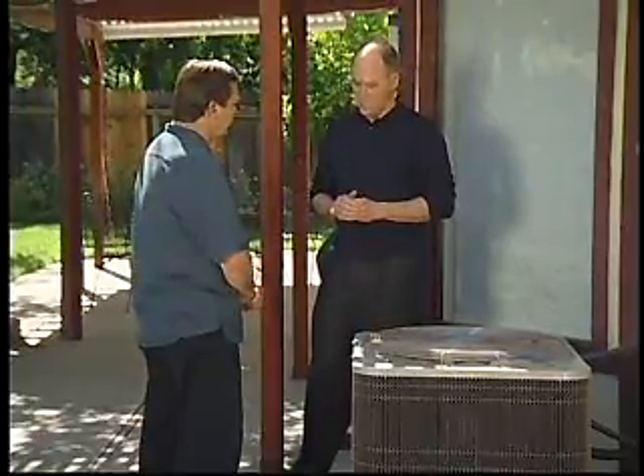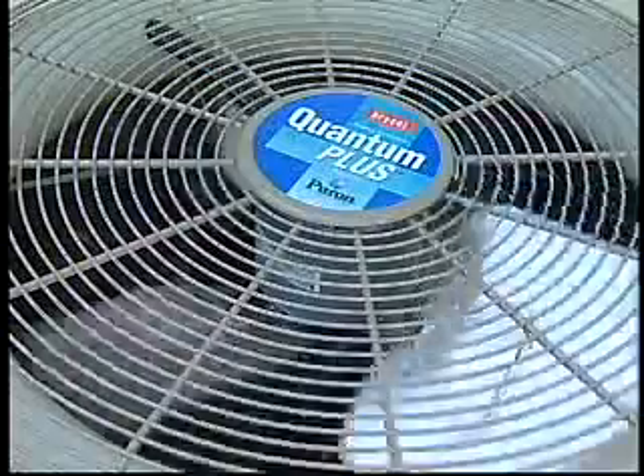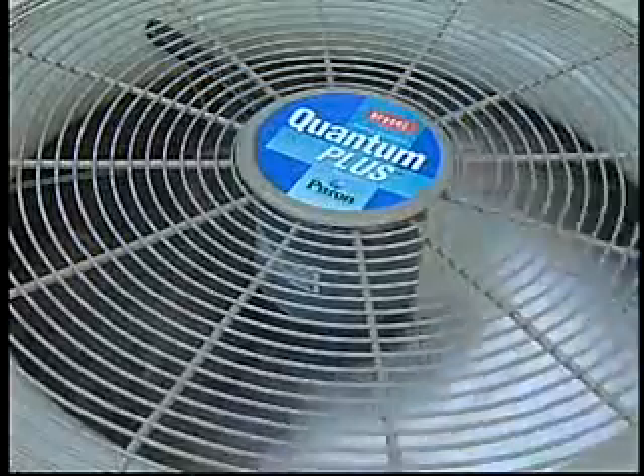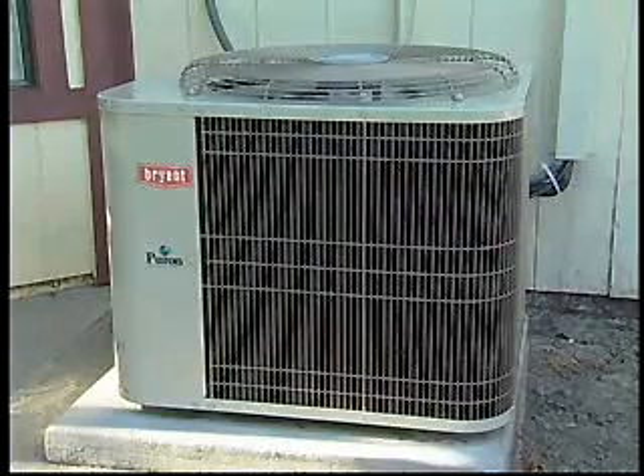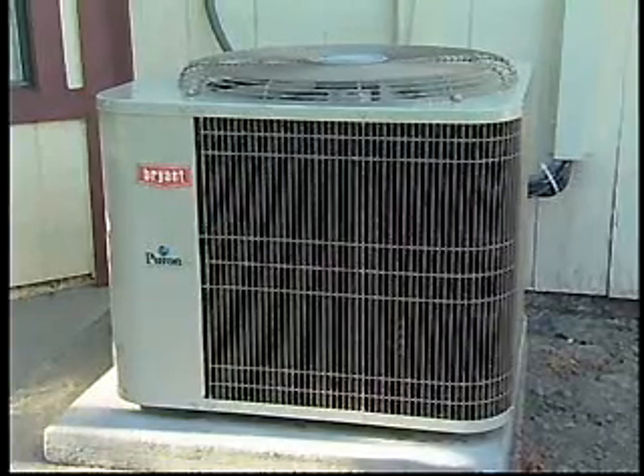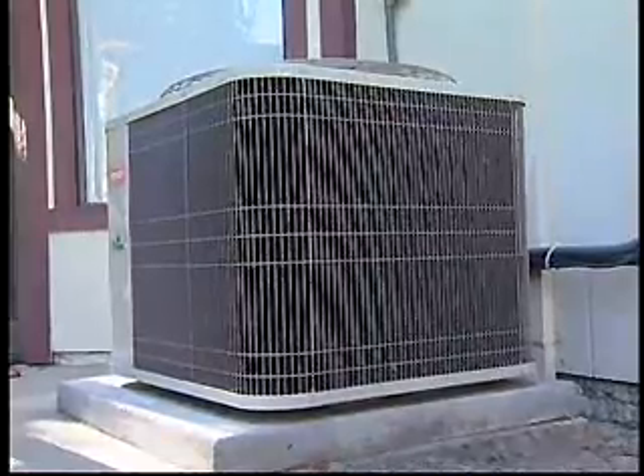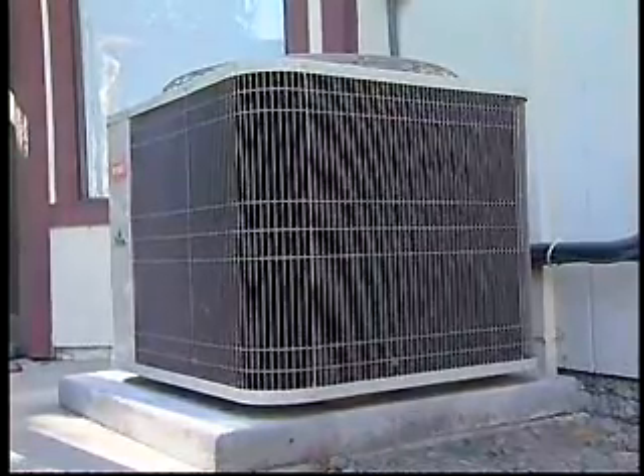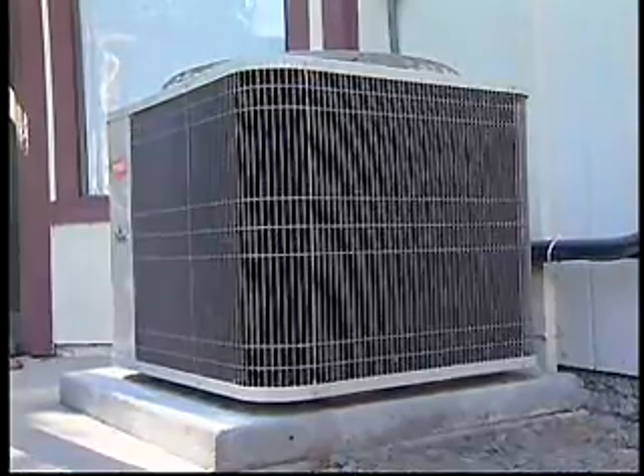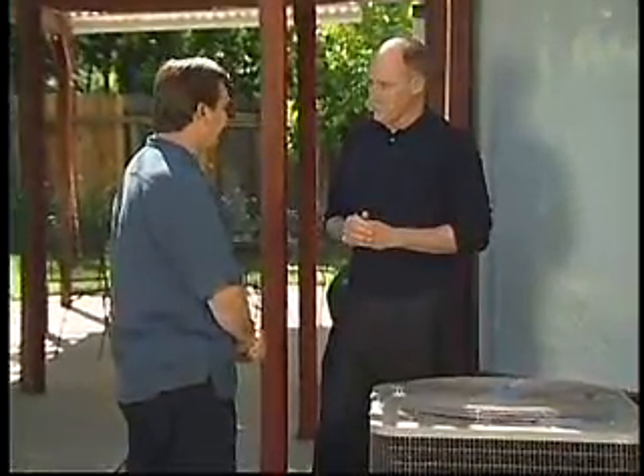What about ductwork installation? Well, ductwork, of course, is a big part, just as you said at the beginning. Having leaky ductwork, I mean, this is a really high efficiency unit we're looking at here, probably a SEER 14 unit. Now, if it's hooked into a standard leaky duct system, you might then be talking about SEER 10. And if you put the wrong amount of refrigerant in, maybe you're talking about SEER 8. And if you get the wrong amount of airflow, maybe you're talking about SEER 7. So you just bought a 14 and you got a 7. Doesn't sound very efficient. No, that's a horrible idea.